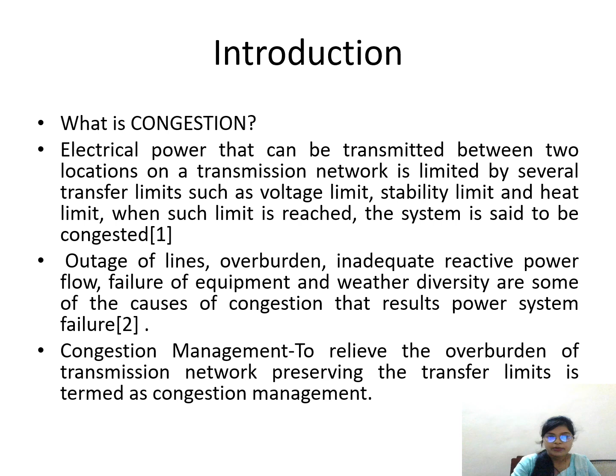Also, it occurs when transmission lines operate beyond their transfer limits, such as voltage limit, stability limit, and heat limit. This occurs due to the outage of lines, overburden, inadequate reactive power, and weather diversity, and also a sudden increment in load. To relieve the overburden in the transmission network, congestion management is used while preserving the transfer limits.